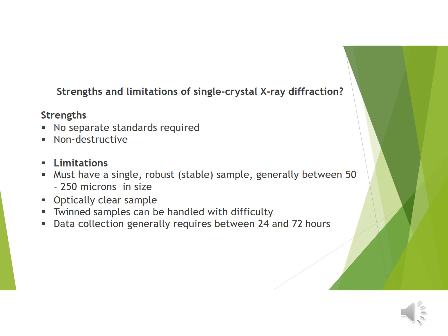Now have a look at the limitations of single crystal X-ray diffraction. We must have a single and stable sample, generally between 50 to 250 microns in size, and the sample must be optically clear, and it is very difficult to handle twin samples. And the data collection generally requires between 24 and 72 hours, so it is a very time consuming technique.